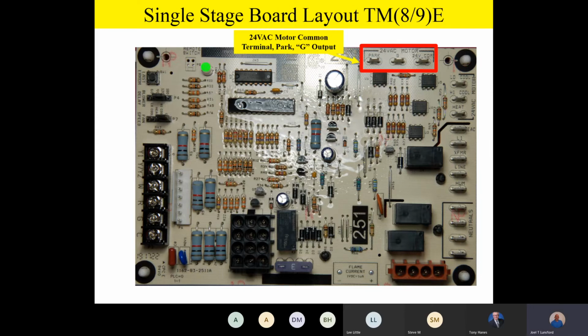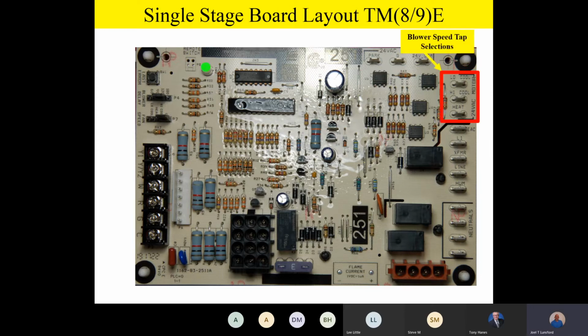Okay, well, let's continue around our control board then. We see that we have some blower speed tap selections: low cool, high cool, and heating speeds. And again, these are all speed wires or speed taps that will go down to the motor that you're going to have to select. Now, from the factory, we always set them up towards the higher numbers, but based on your ductwork, make sure that you select the speed according to give you the proper airflow.